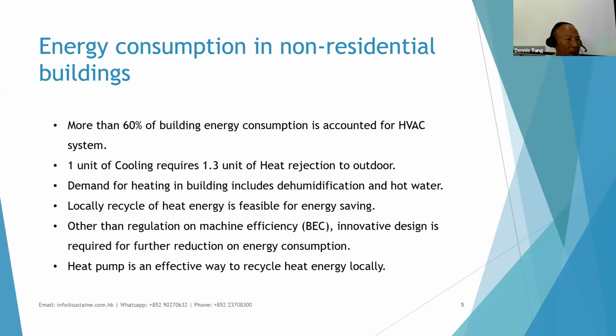In Hong Kong, the government together with the EMSD has already issued a regulation, the building energy code, which has specifications on the minimum efficiency of machinery, the design criteria, and the materials used to minimize the amount of energy used in HVAC systems. Other than that, in order to further reduce energy consumption in buildings, innovative design is much more demanding. With innovative design, we can reduce energy consumption and provide a better environment for our future. I would like to focus on heat pumps, because a heat pump is currently a very effective way to recycle heat energy locally inside the building.